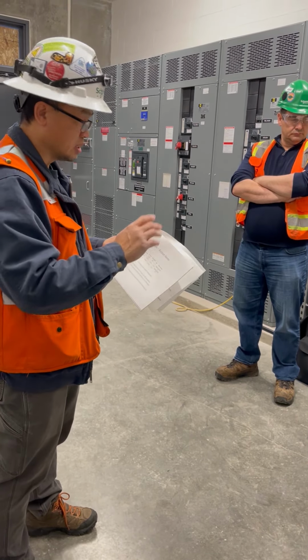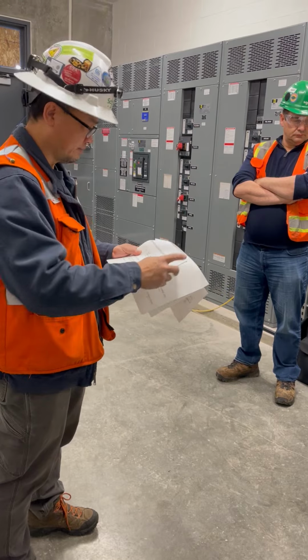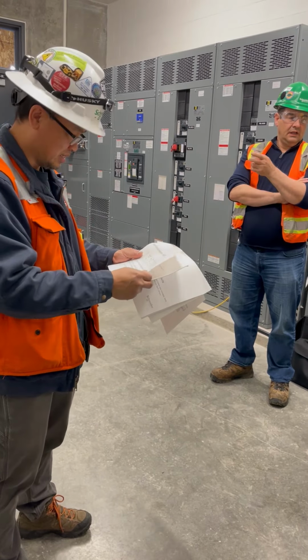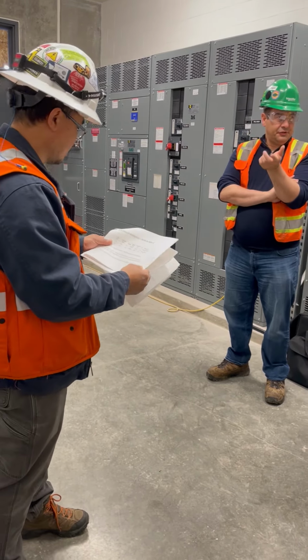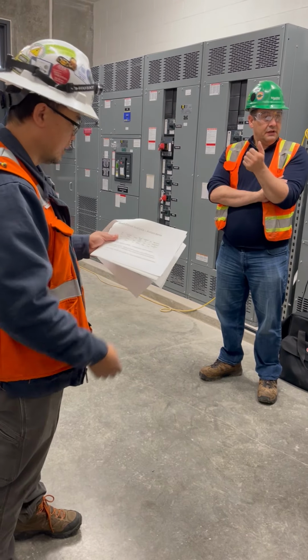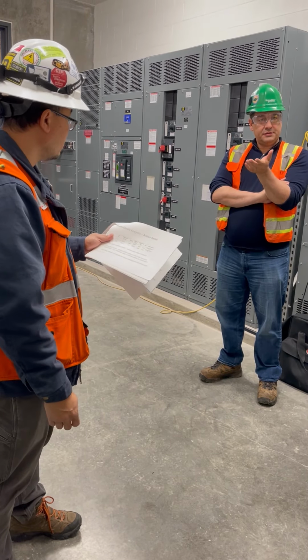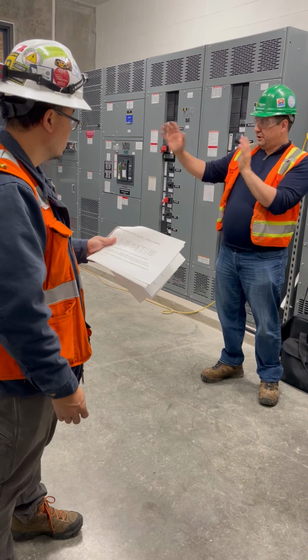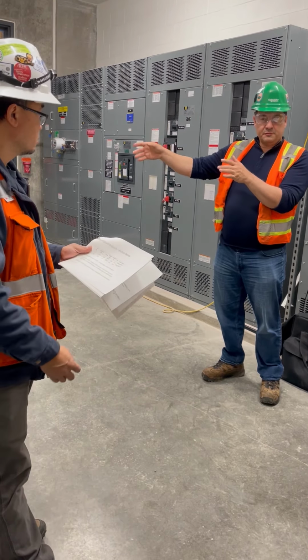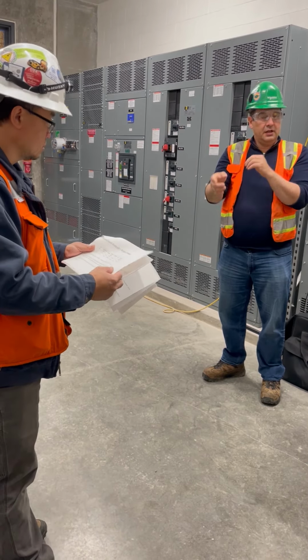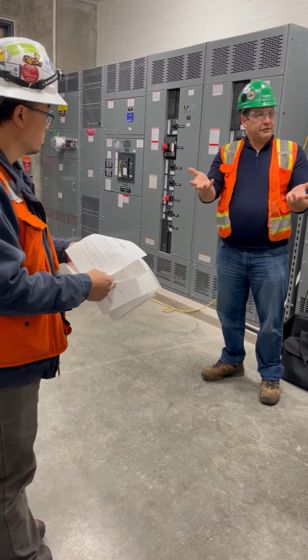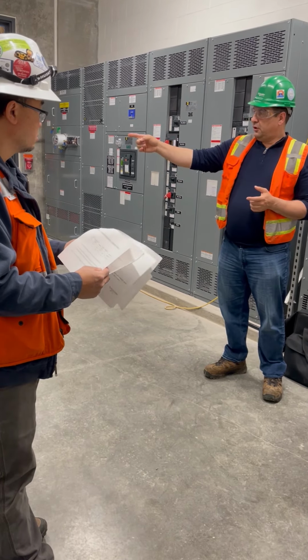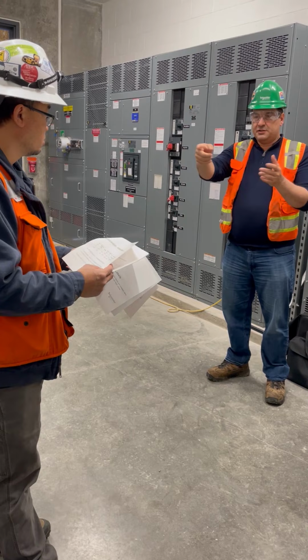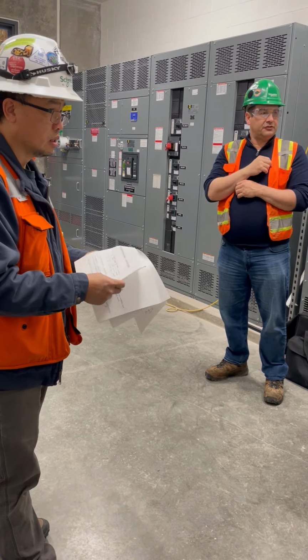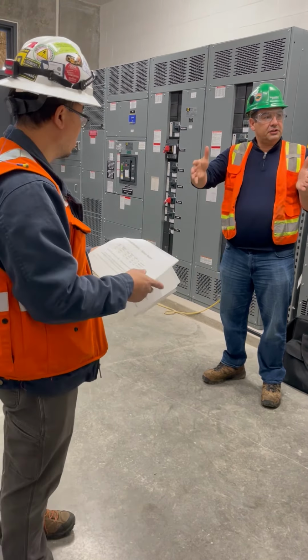I haven't seen it, but tests prove it, right? That's why we have this, and that's why we do this. The table he just looked at is going to be the short circuit coordination study. Yep. So eventually, when you get your own amps, you will have the operating procedures for the switchboard, but you also have the full study. Those are the tables that you need to reference, and you also need to know the labels. We'll go over that in a second, but I just want to reference that when you get that, you'll get those tables, and they're specific to this location.